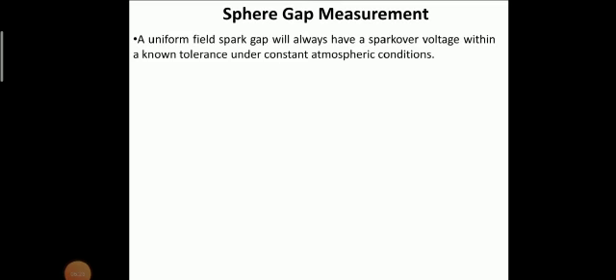Sphere gap measurement. A uniform field spark gap will always have a spark over voltage within a known tolerance under constant atmospheric conditions. I showed you this when I was explaining what is meant by a sphere gap or a spark gap. Therefore a spark gap can be used for the measurement of the peak value of voltages if the gap distance is known. You will understand this when we go through the laboratories, the HV labs.